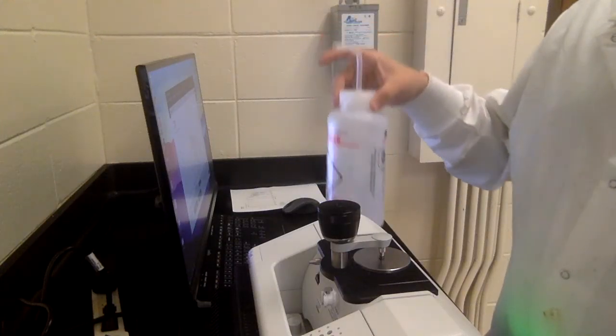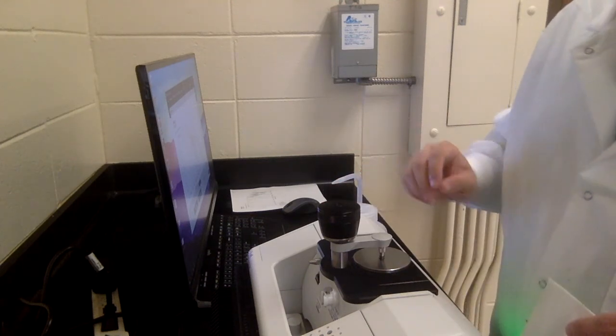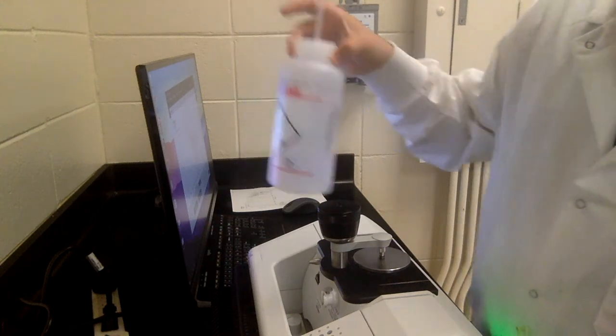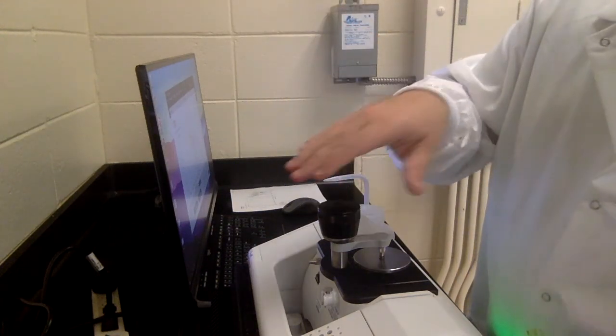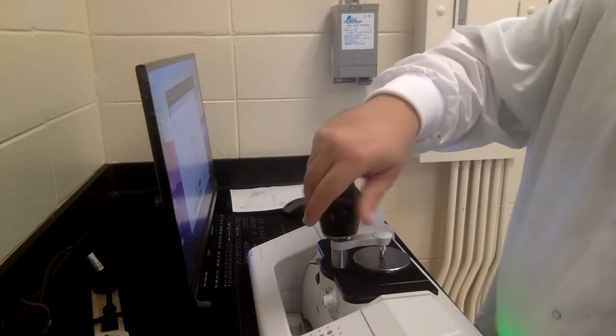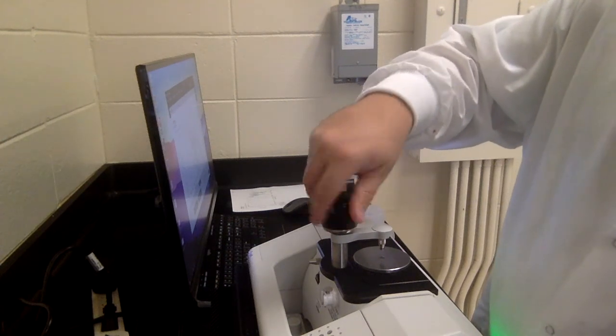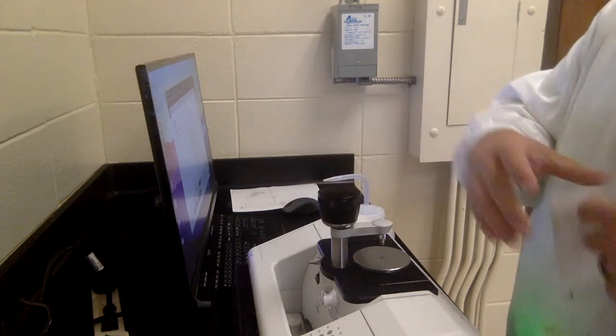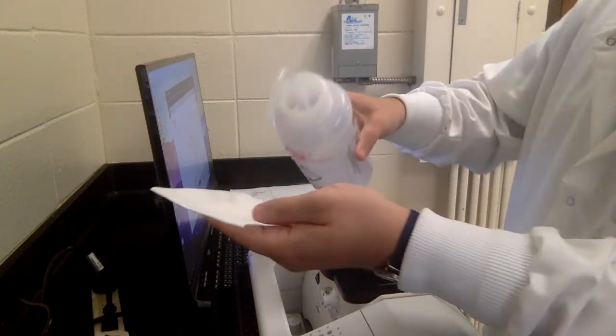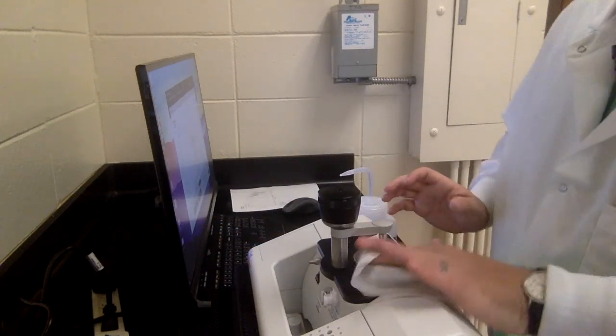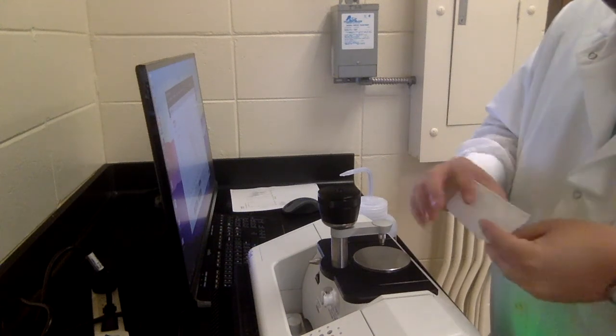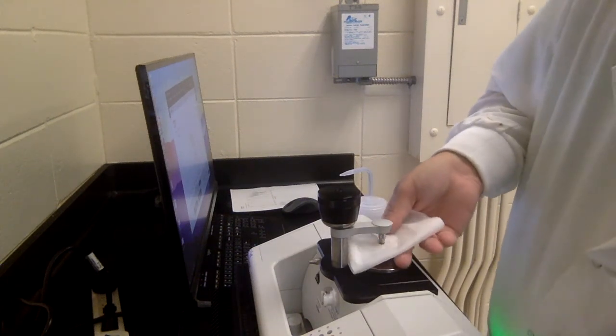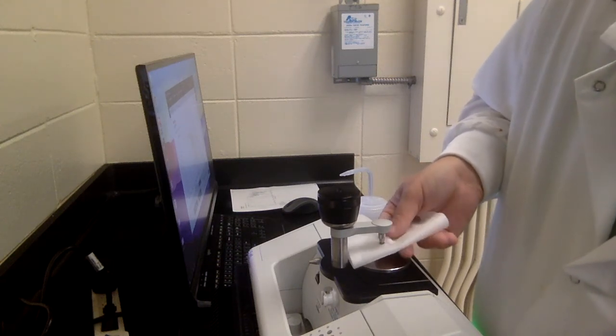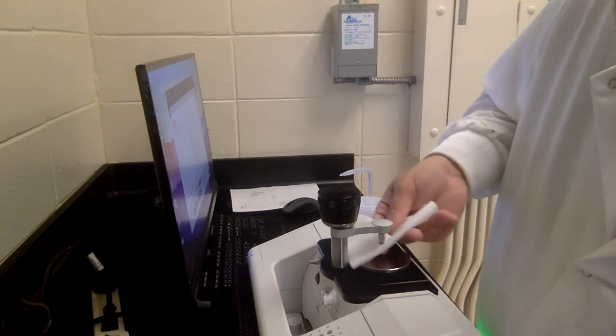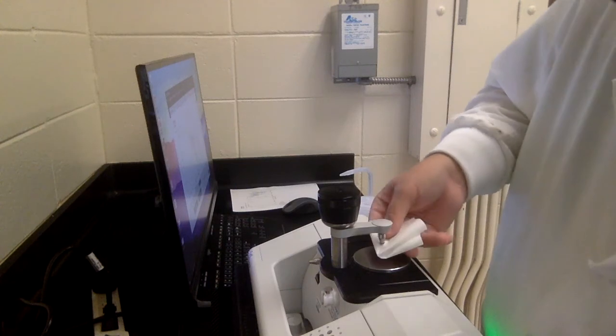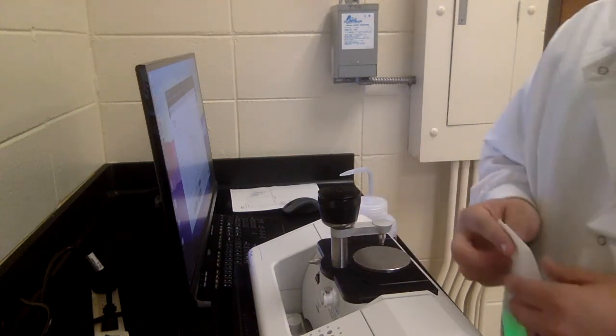After every use, you have to make sure that you clean off the detector. You can use either acetone or methanol to do so. You cannot get this sample back, but you do have to clean it off. So now you just wind this up just how you did when you pushed it down. You just do it the opposite way. A chem wipe with some acetone on it, and you just make sure that that surface is rid of your sample. And make sure that you get the arm as well, as there may have been some transference of your compound onto it. And now the IR is ready for the next sample.